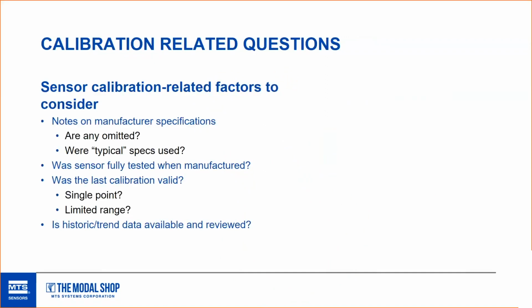when assessing risk, it's important to think about some often overlooked calibration-related factors. Were any on your recalibration or your initial calibration, were any specs omitted? Were there typical specs used? Was the sensor really fully tested when it was made? Was the last calibration good? Was it just done at a single point or a limited range? Is there historic or trend data available, and is it reviewed?